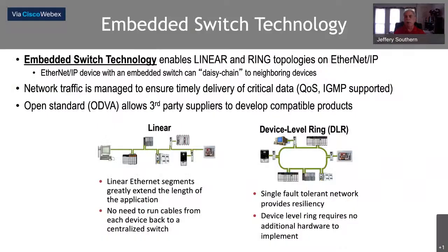A device level ring is an embedded switch technology that allows us to communicate with resilient media. In a linear bus, if I disconnect one of these cables, the devices downstream can no longer communicate. But if I have them in a ring, I can survive one media failure or one device failure and still talk to everything else in the ring.